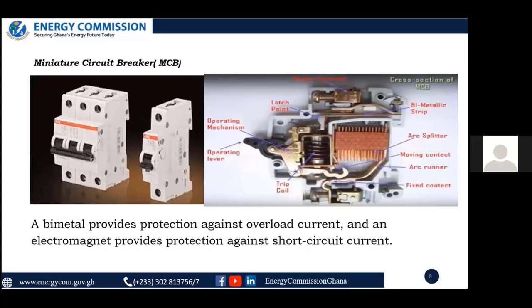So you see the bimetallic at the right-hand side, where the cross-section of the miniature circuit breaker is drawn. There's a bimetallic strip there. When this current, which is over the rated current, passes through the MCB, it heats the strip and causes it to bend. Once it bends, there's a latching point there, and it activates the operating mechanism. The operating mechanism is connected to the fixed contact, and the fixed contact responds. So it all starts with a bimetallic for overload currents. Once it gets heated, it bends and initiates the process for it to trip.